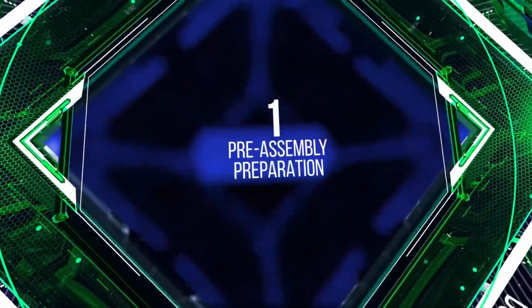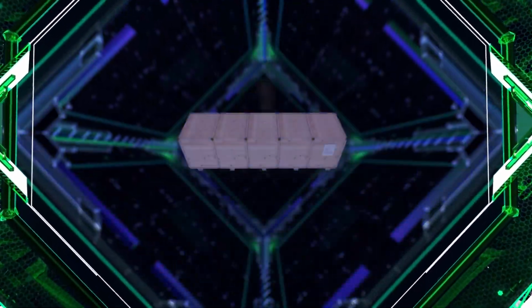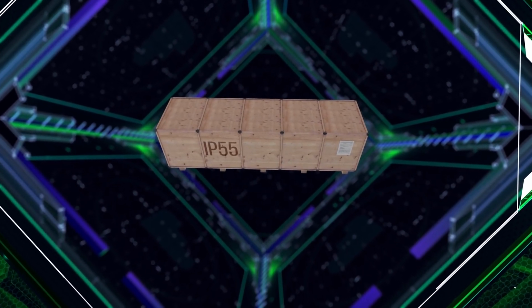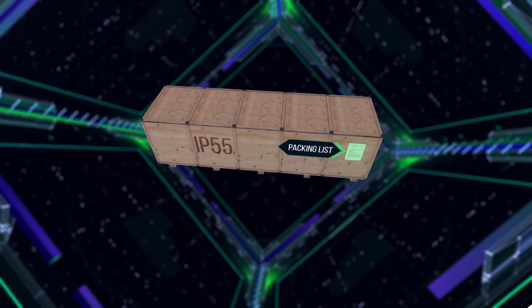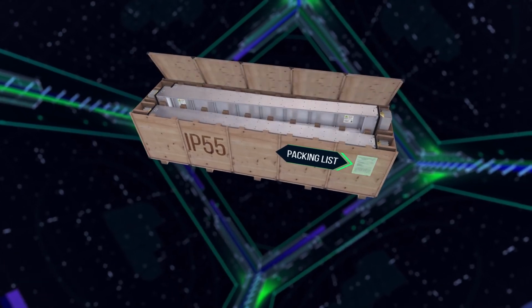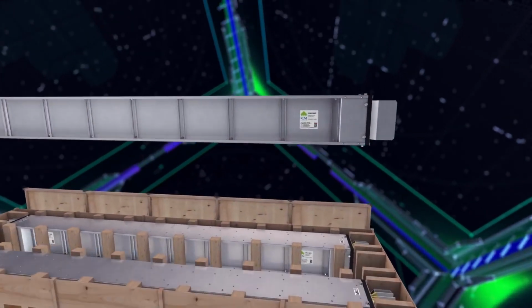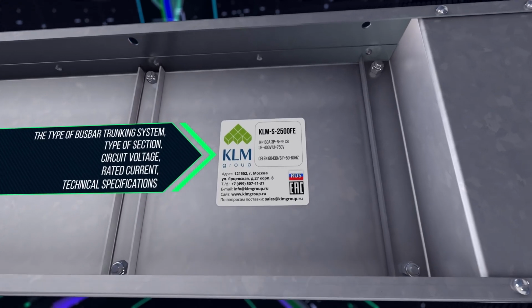Pre-assembly preparation. The sections of the KLM busbar trunking system are delivered to the installation site in factory packaging, on pallets or in cases. The packing lists indicate the items contained inside. Tags on sections indicate the parameters of the busbar trunking system.